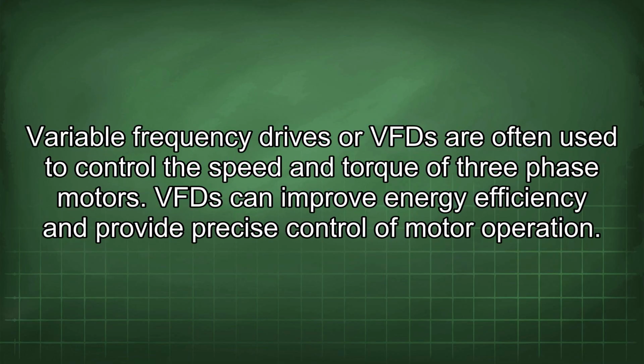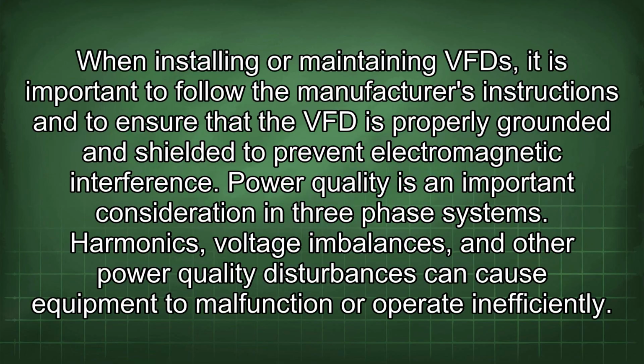Variable frequency drives, or VFDs, are often used to control the speed and torque of three-phase motors. VFDs can improve energy efficiency and provide precise control of motor operation. When installing or maintaining VFDs, it is important to follow the manufacturer's instructions and to ensure that the VFD is properly grounded and shielded to prevent electromagnetic interference.